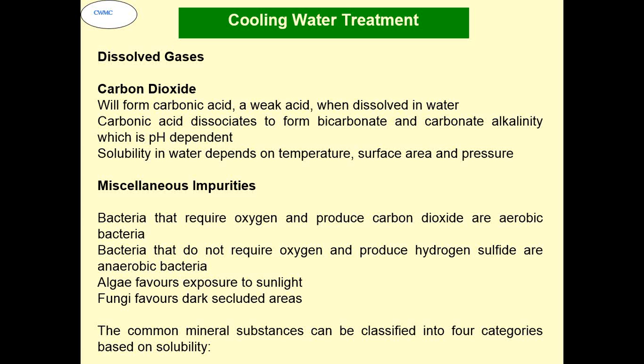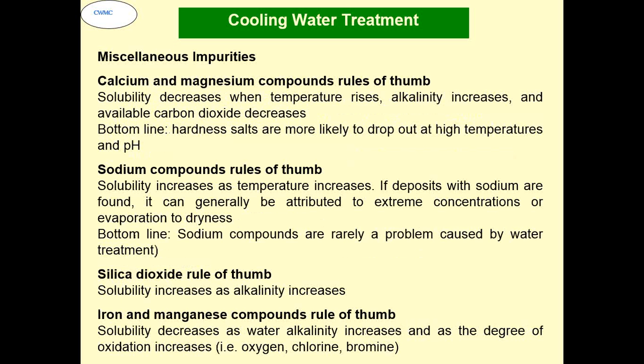The common mineral substances can be present in four categories based on solubility. For calcium and magnesium compounds, solubility decreases when temperature rises, alkalinity increases, and available carbon dioxide decreases. Hardness salts are more likely to drop out at high temperature and pH. Sodium compounds increase in solubility as temperature increases. If deposits with sodium are found, it can generally be attributed to extreme concentrations or evaporation to dryness. Bottom line, sodium compounds are rarely a problem caused by the water treatment. For silica dioxide, the rule of thumb is that solubility increases as alkalinity increases. For iron and manganese compounds, solubility decreases as the water alkalinity increases and the degree of oxidation increases, for example with the presence of oxygen, chlorine or bromine.